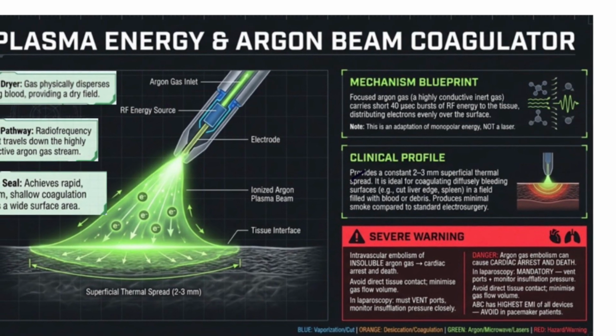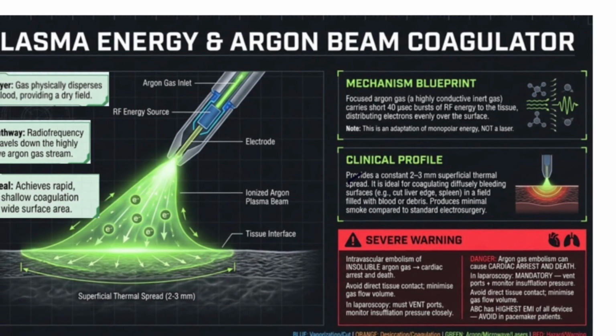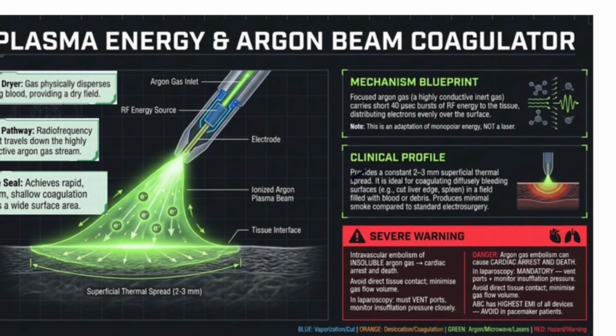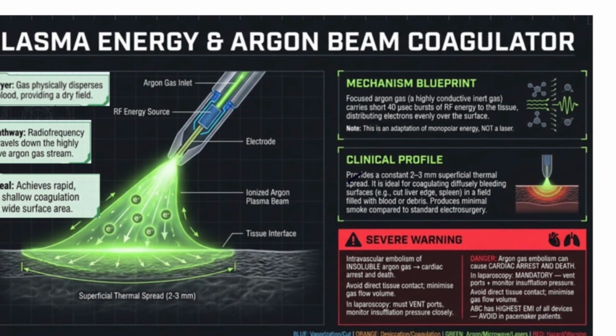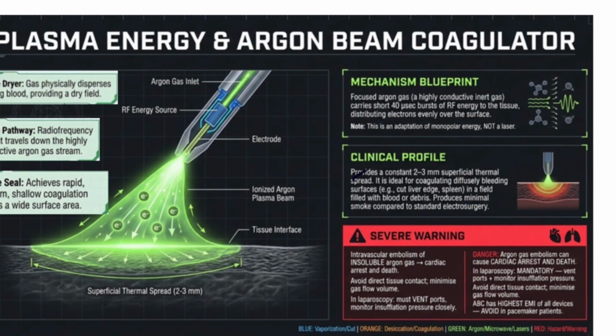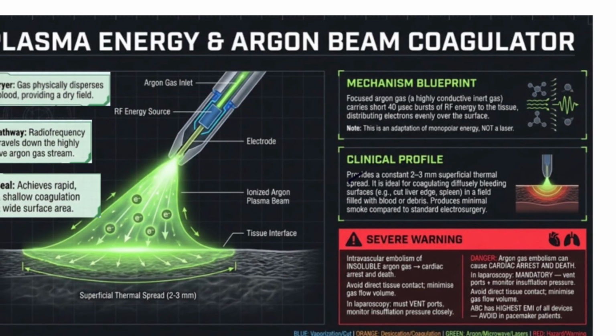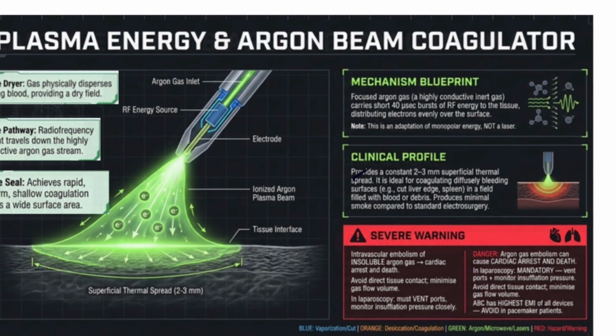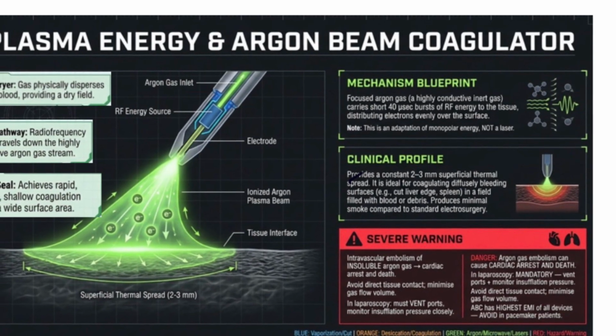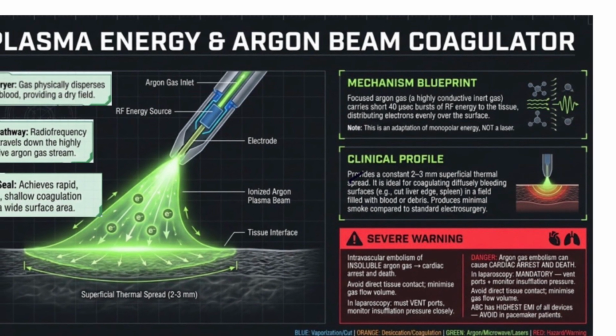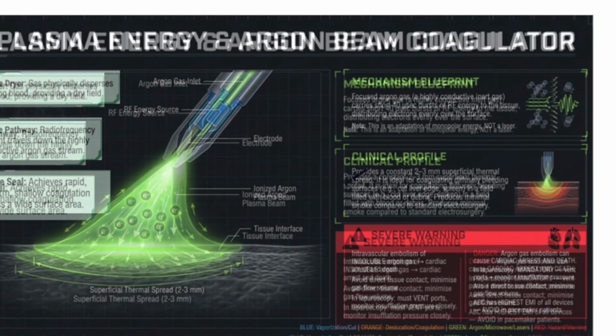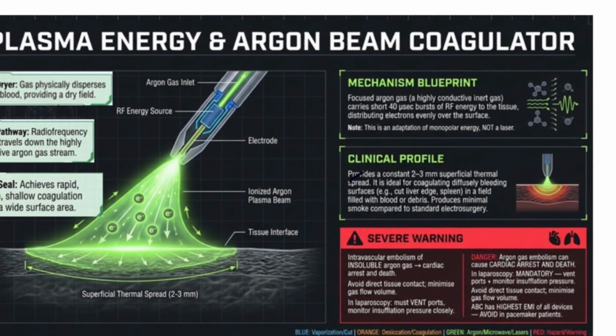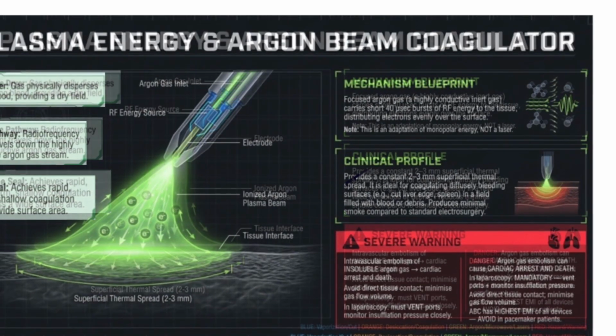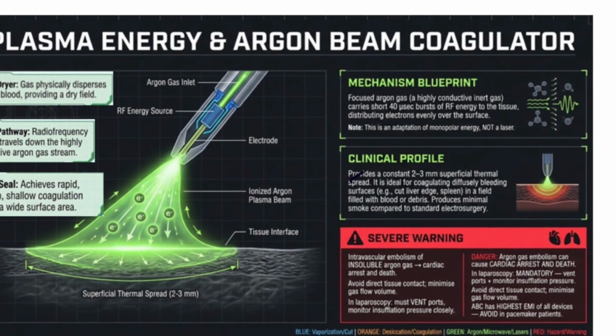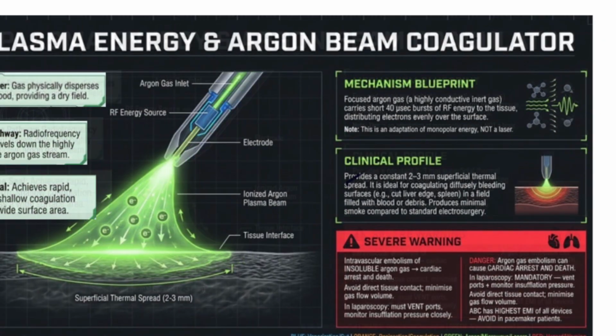The plasma energy, that is the APC, argon beam coagulator. The gas physically clears the pooling of the blood, providing a dry field. Radio frequency current travels down the highly conductive argon gas stream. The seal achieved is rapid, uniform, shallow coagulation across a wide surface area. The mechanism: the focused argon gas, a highly conductive inert gas, carries short 40 microsecond bursts of radio frequency energy to the tissue, distributing electrons evenly over the surface.